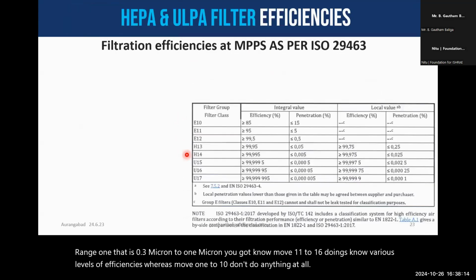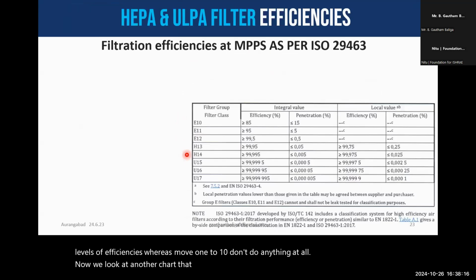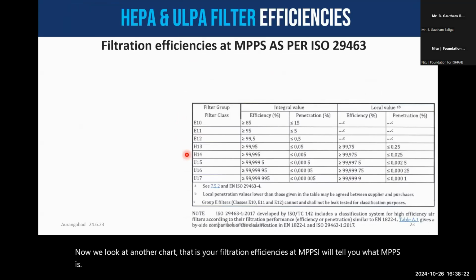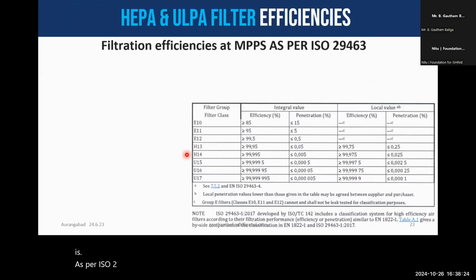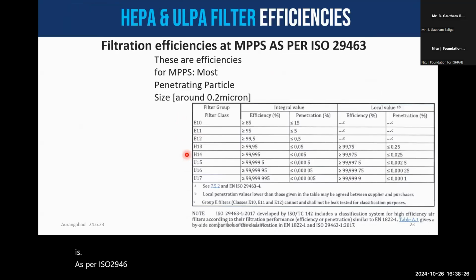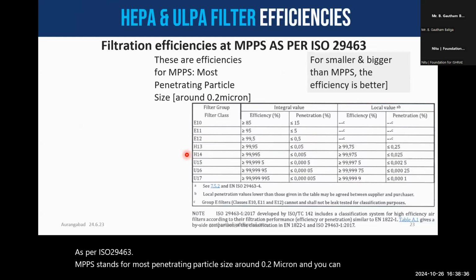Now we look at another chart, that is your filtration efficiencies at MPPS. I'll tell you what MPPS is. As per ISO 29463, MPPS stands for most penetrating particle size, around 0.2 micron. And you can see this particular chart.